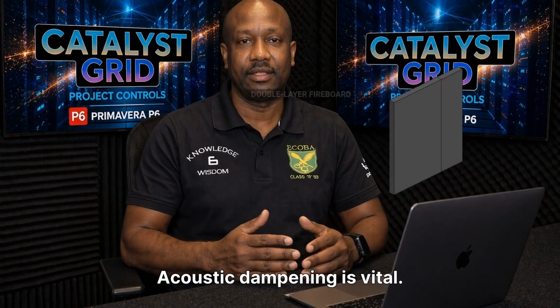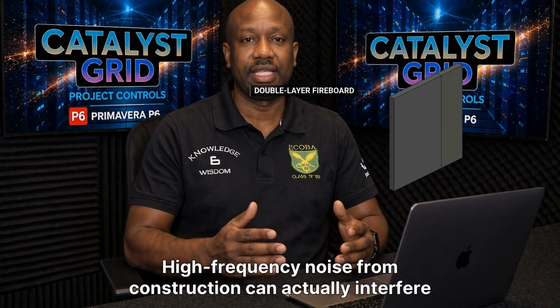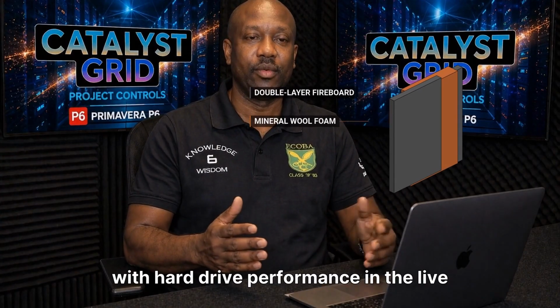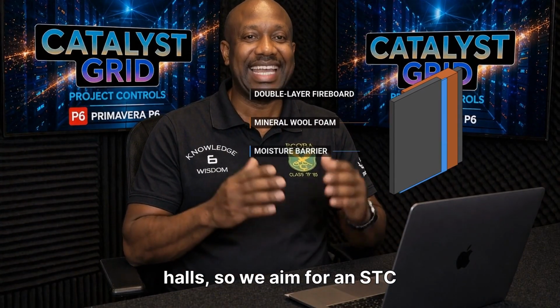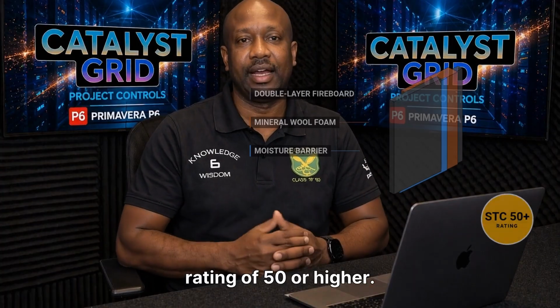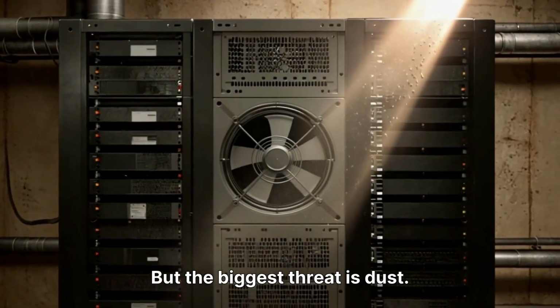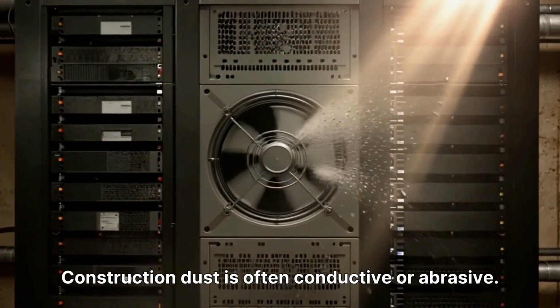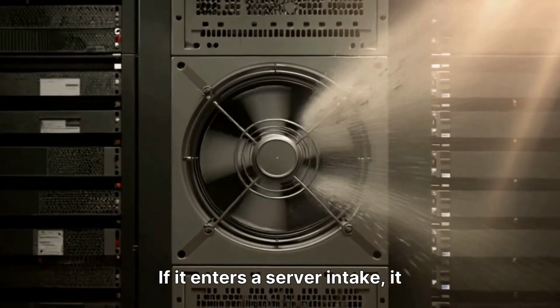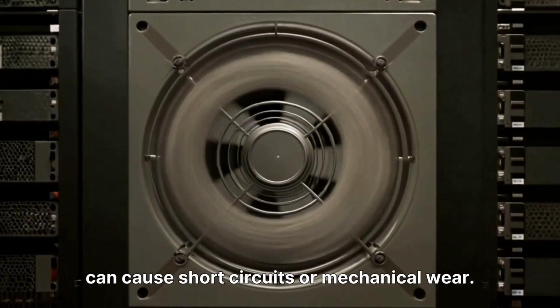Acoustic dampening is vital. High-frequency noise from construction can actually interfere with hard drive performance in the live halls, so we aim for an STC rating of 50 or higher. But the biggest threat is dust. Construction dust is often conductive or abrasive. If it enters a server intake, it can cause short circuits or mechanical wear.